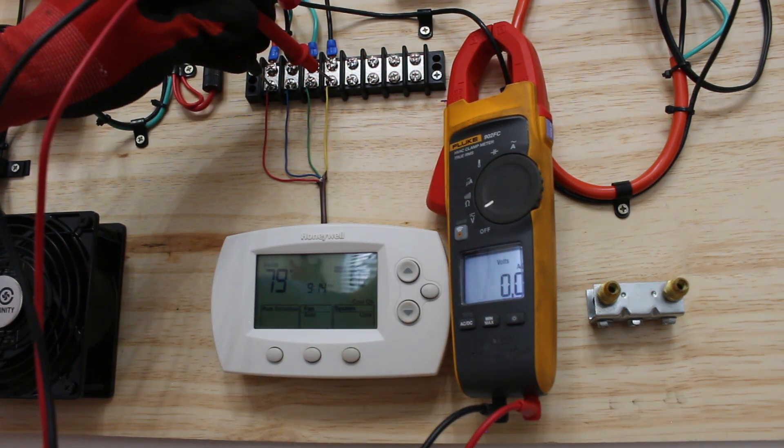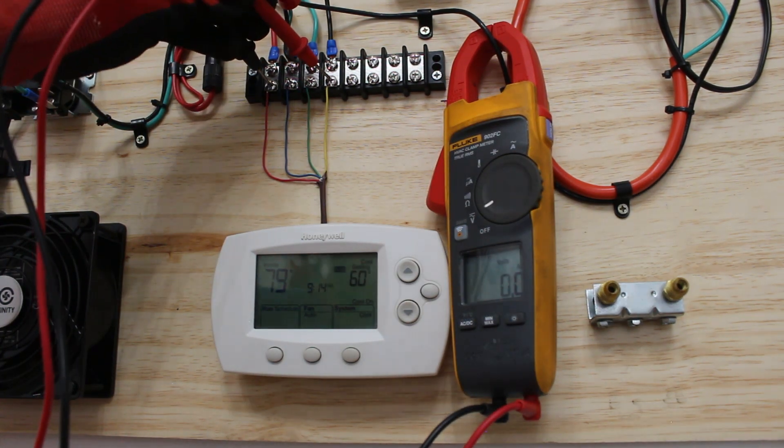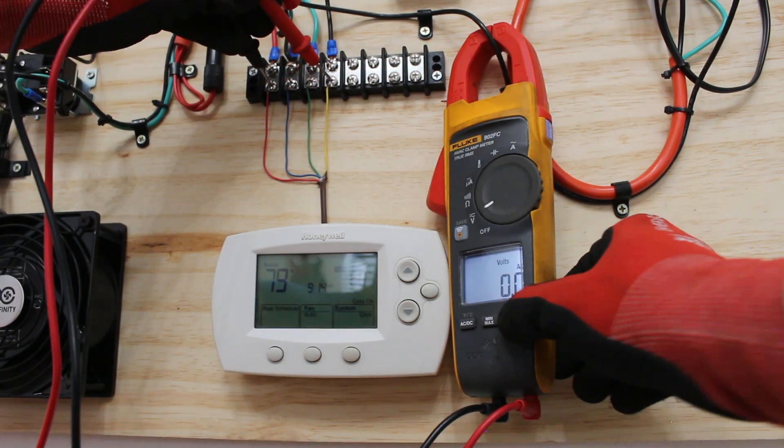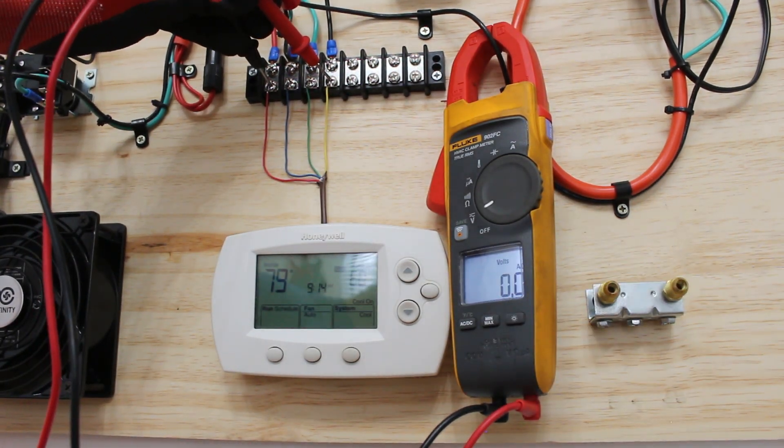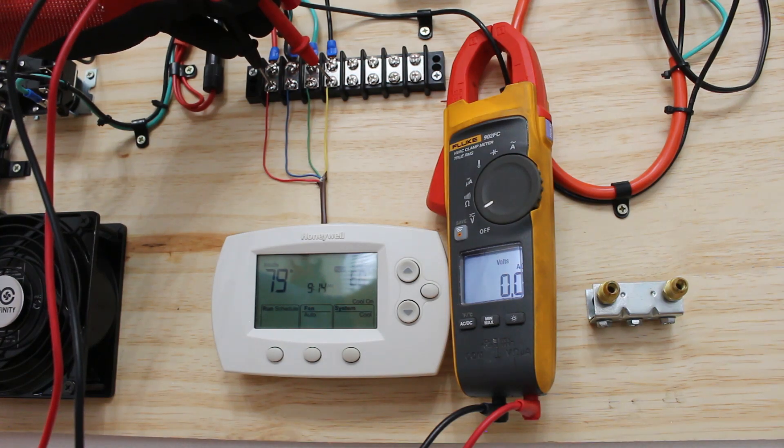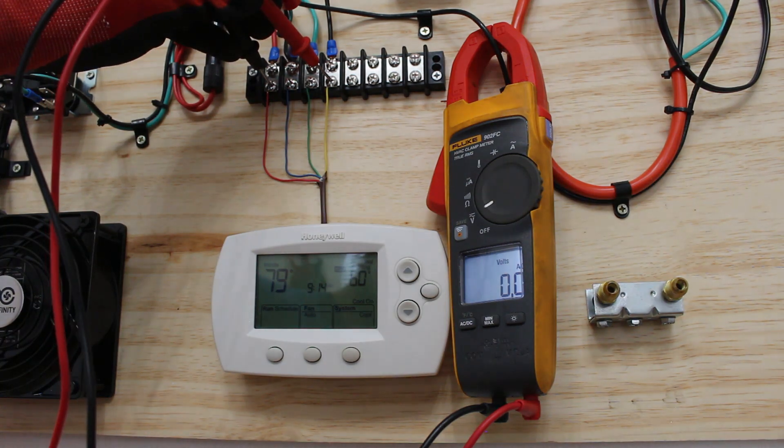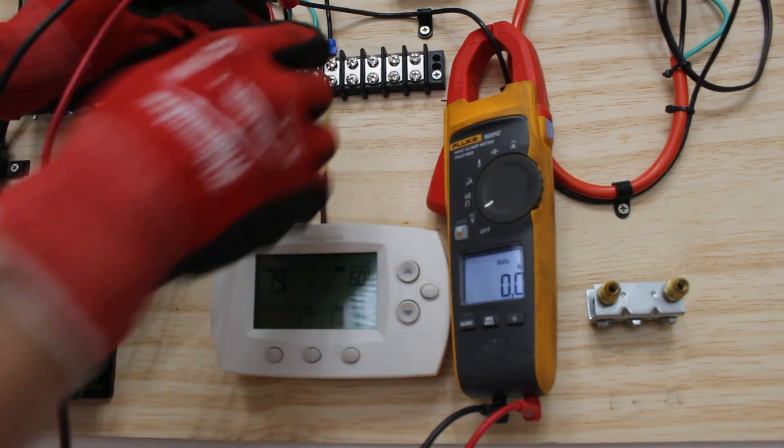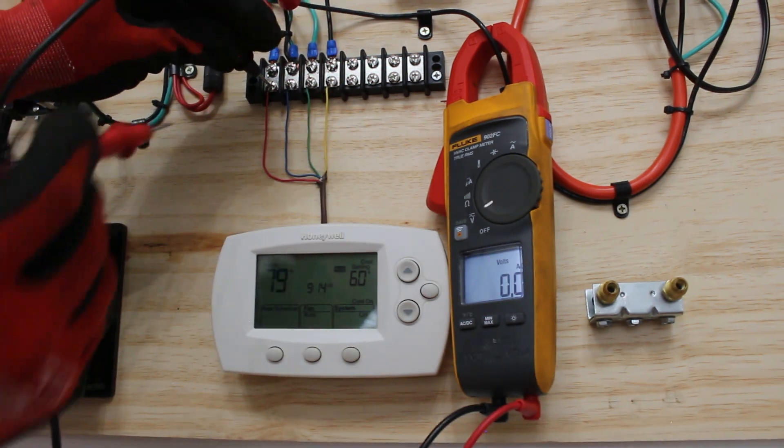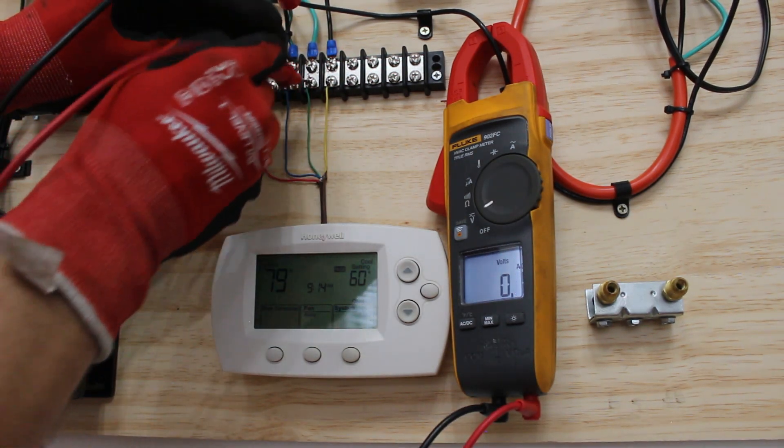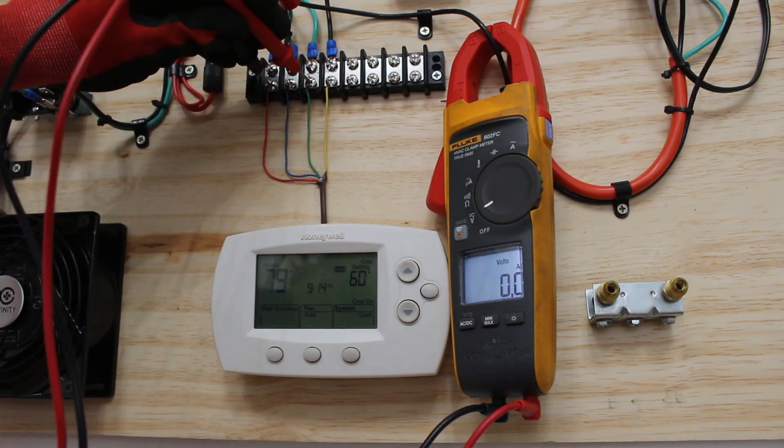As you can hear our indoor fan started. Right now we have our meter across R and Y. You can see we had our voltage drop, now we have zero volts. That means the circuit closed and the thermostat is doing its job. Of course we hear the fan running but that should also have zero volts because now our circuit is closed as well.